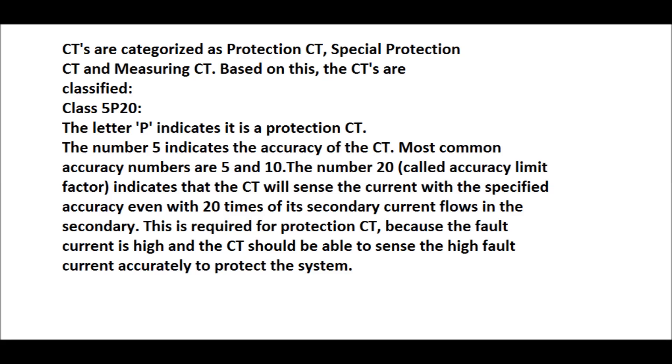CTs are categorized as protection CT, special protection CT and measuring CT based on these. CTs are classified as 5P10 or 5P20 such as the letter P indicates in this case as a protection CT. The number 5 indicates the accuracy of the CT. Most common accuracy factor are 5 or 10.